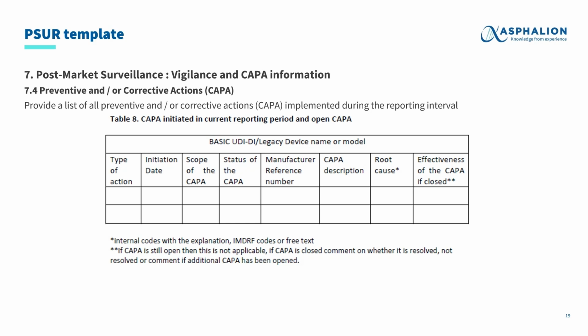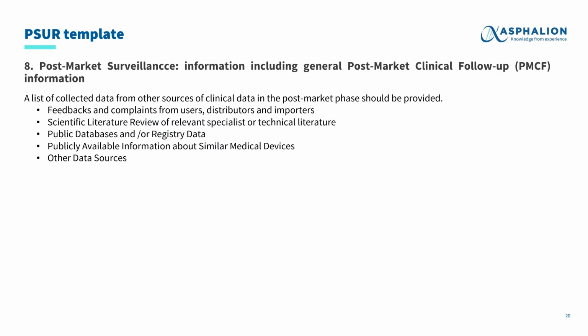After that, two sections focused on clinical data should be included, which means all information gathered from post-marketing clinical follow-up activities. First of all, we will include a general section to describe all clinical data obtained from feedback and complaints from users, distributors, or importers. Also, any clinical data obtained from the scientific literature review of relevant specialist or technical literature, any clinical data from public databases or registry data, also any relevant information about similar medical devices that could be of interest to determine the benefit-risk profile of our medical device, and any other clinical data from any other data source that could be relevant for the PSUR of the medical device.